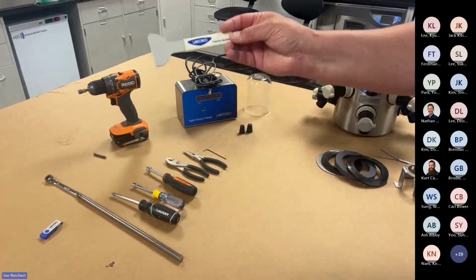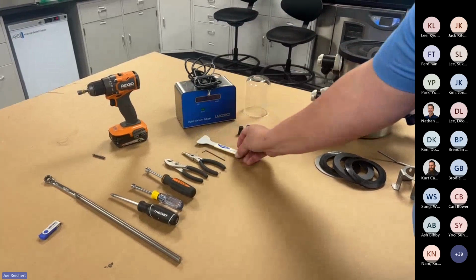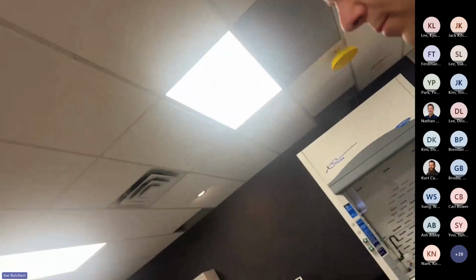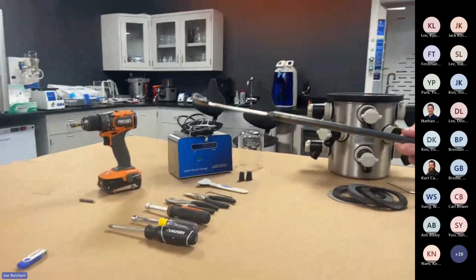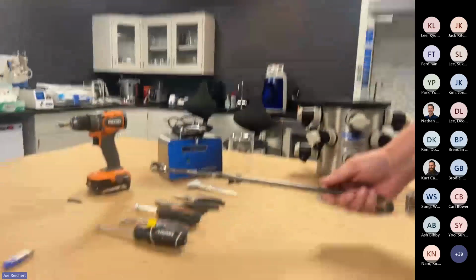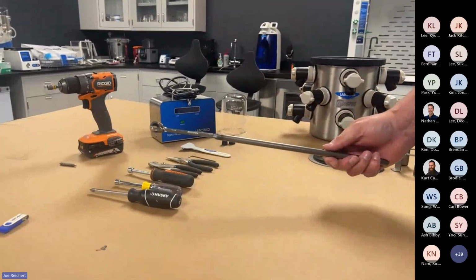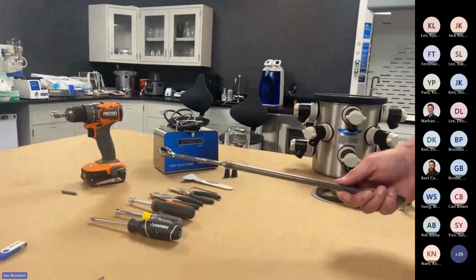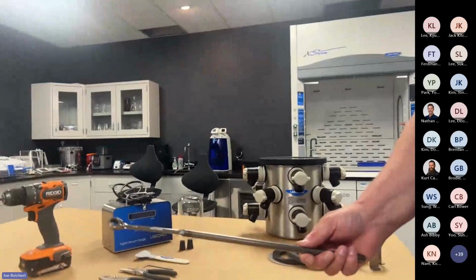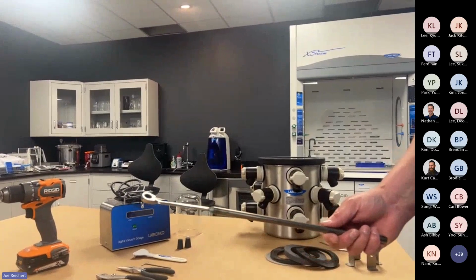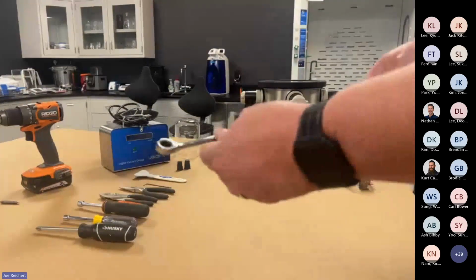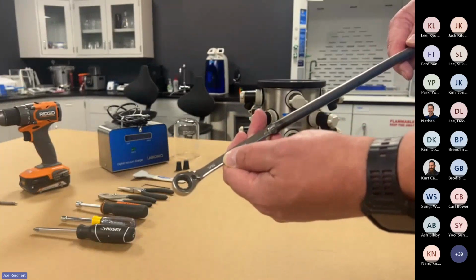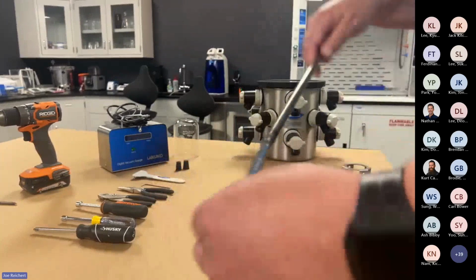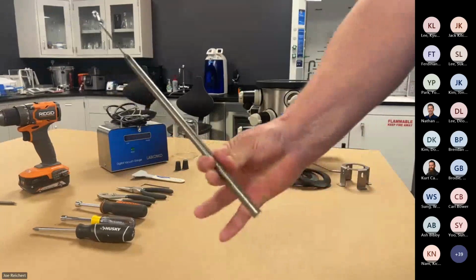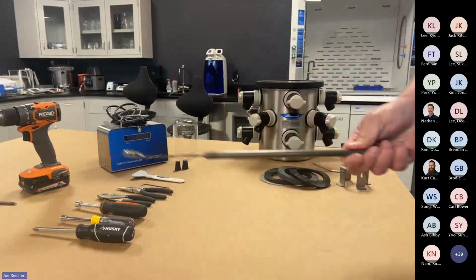I'll show you what people actually do use the valve wrench for, what it should be used for. And then your drill, vacuum gauge. We also have a specialty tool that we kind of made ourselves. This really helps with getting the nuts from the chamber on the roof of the freeze dryer. It's a long reach in there sometimes, and on the 2.5 liter machines, it is very small to get along the sides. So it is basically just a 7/16 ratcheting wrench welded onto a steel rod, just so we can reach in there. Something simple to make.